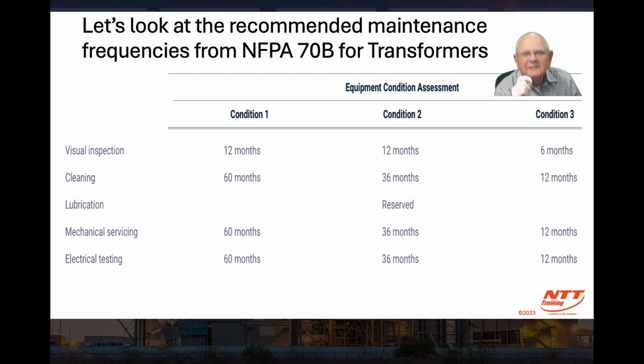Now take a look at electrical testing. If it's condition 1, in great shape, environment's fine, not a critical piece of equipment, I only have to run electrical tests every 5 years... sorry, every 36 months if it's condition 2. But because our equipment condition came out as a 3, due to that criticality, we have to do electrical testing every 12 months on that piece of equipment. So that's how we determine the frequency for our electrical equipment.